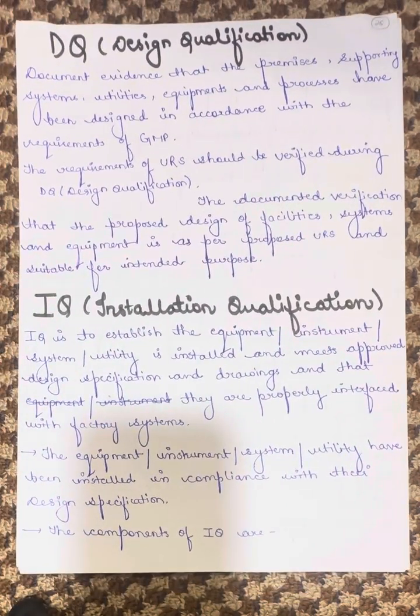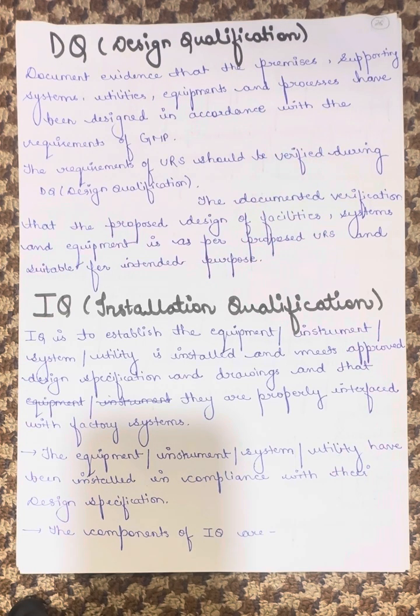DQ stands for Design Qualification, where document evidence that the premises, supporting system, utilities, equipments and the processes have been designed in accordance with the requirement of GMP. The requirement of URS should be verified during the DQ, during the design qualification.